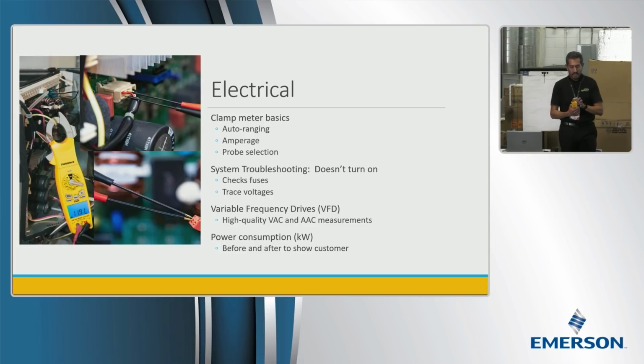Now, on amperage: on the back of a clamp meter's clamp, you typically see some arrows. What do those arrows mean? Does anybody know? Typically, these arrows help you follow best practices on where to position a wire when taking a measurement, to get an accurate clamp reading. Usually you'd want the wire in the center of the clamp for the most accurate reading. However, one benefit of the Fieldpiece clamp meter is that the clamp is designed so accuracy doesn't vary much no matter where you put the wire. That's particularly useful because you don't want to be stuck holding the clamp meter perfectly still on the wire among a bunch of other wires just to get it centered. You want to clamp it, hang it, and let it do its measurement.